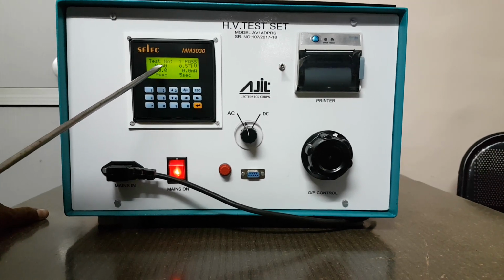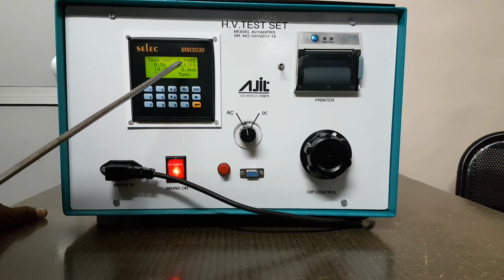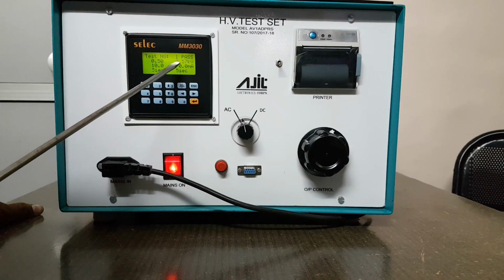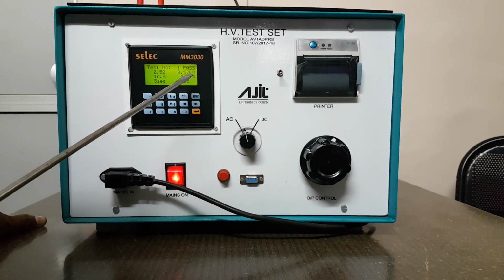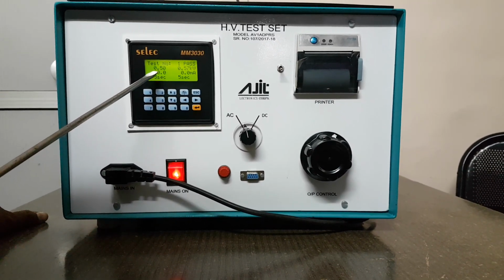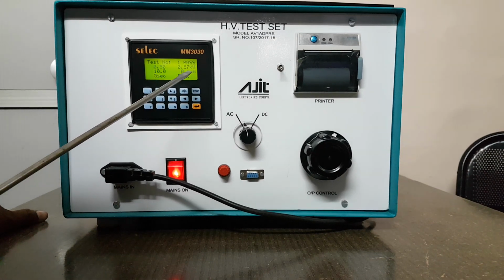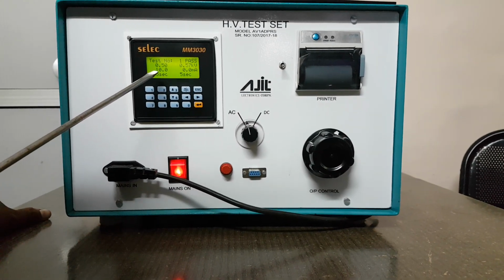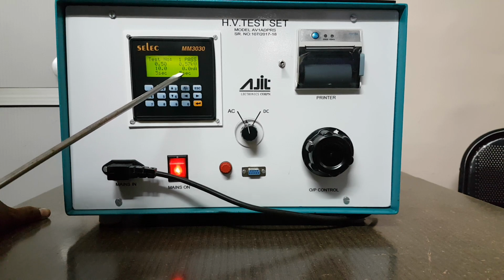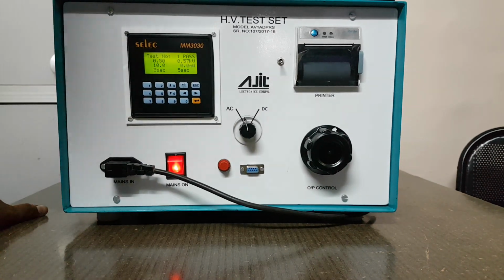Set value was 0.5 kV. Actual output was 0.57 kV. Leakage current set was 10 milliampere. Actually there was no leakage current. Set time was 5 seconds and lapse time was 5 seconds. These are the test results.